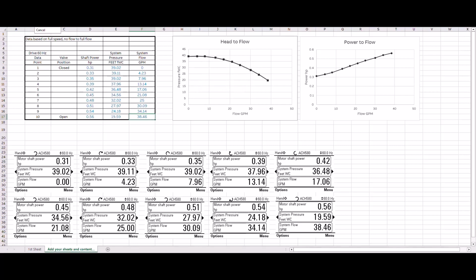We have some rules that we have to follow, and one of the rules is the power rule. Power 1 must be less than power 2, less than power 3, less than power 4. If you look at that, power in data point 1 is 0.31 horsepower. Power in data point 2 is 0.33, and power in data point 3 is 0.35. As we go through all our 10 points, we follow this rule. That's good news.